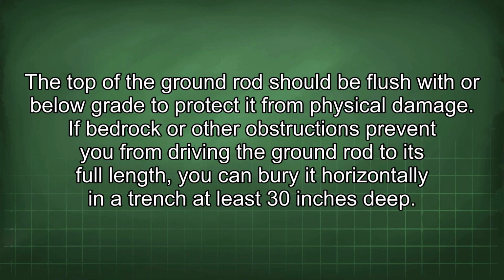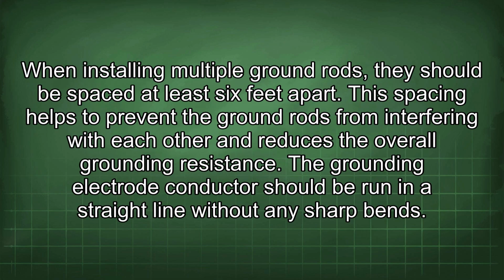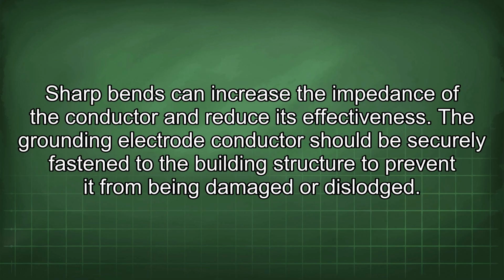If bedrock or other obstructions prevent you from driving the ground rod to its full length, you can bury it horizontally in a trench at least 30 inches deep. When installing multiple ground rods, they should be spaced at least 6 feet apart. This spacing helps to prevent the ground rods from interfering with each other and reduces the overall grounding resistance. The grounding electrode conductor should be run in a straight line without any sharp bends. Sharp bends can increase the impedance of the conductor and reduce its effectiveness.